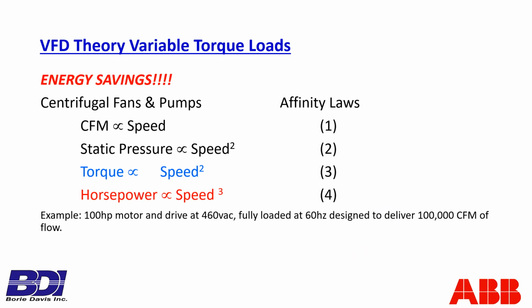All right, so here are our centrifugal loads, and they operate by a unique set of laws due to the shape of the impellers. The laws are called the affinity laws, and they relate speed and pressure or torque and power together relative to speed. And this is where the big energy savings is. And if you think about the loads in a specific building, commercially, these are the largest loads in the building, your large pumps and fans, chillers, etc.